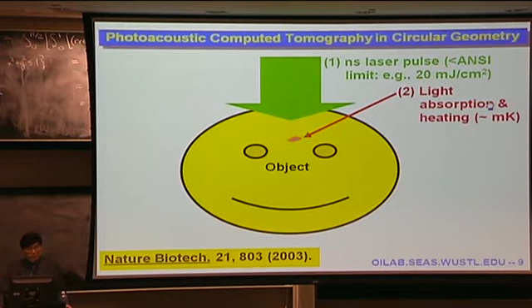The key difference between ballistic optical imaging and our method is we allow photons to scatter, because that's the only way to penetrate deep into biological tissue. Any photons are useful photons because as long as light is absorbed, it'll be converted at least partially into heating. For every millidegree temperature rise, through the photoacoustic effect, we can produce 8 millibars pressure rise, which is already above the noise level for our photoacoustic ultrasound detectors.